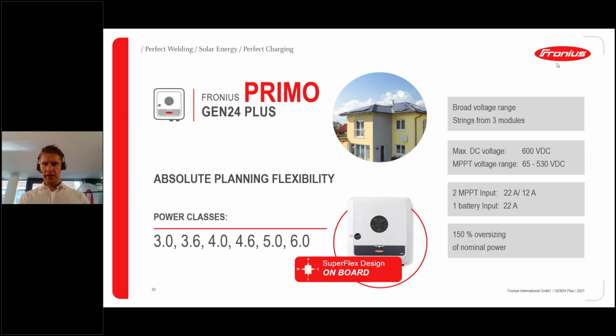Strings from 3 modules on are configurable. You see here the MPPT voltage range is really low, beginning from 65 up to a max of 530 volts DC - that's the MPPT voltage range. The maximum DC voltage is up to 600 volts DC. The MPPT currents I already mentioned, and important to Superflex design is also the DC-AC ratio, meaning 150% of over-dimensioning on the DC side is possible.